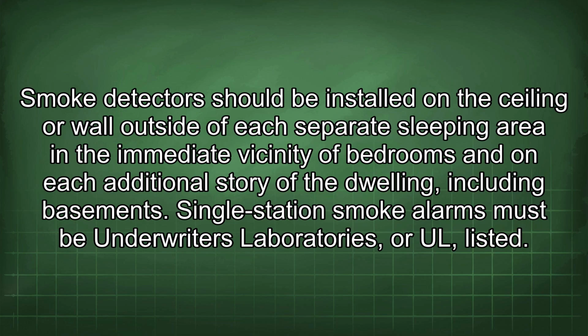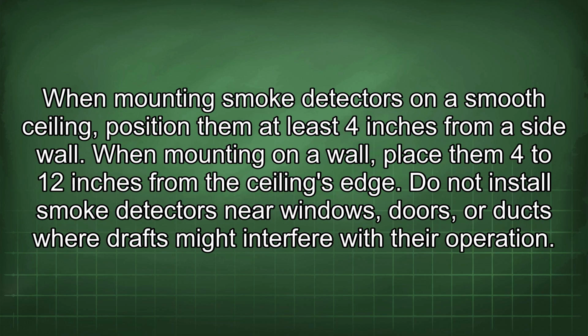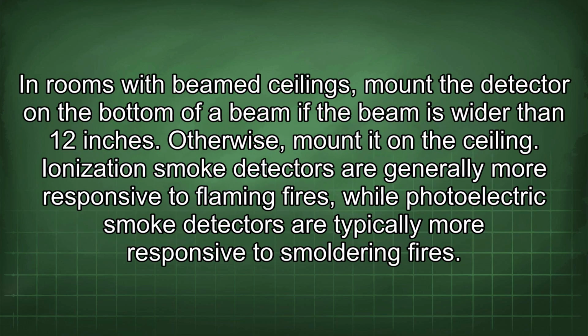Single-station smoke alarms must be Underwriters Laboratories, or UL, listed. When mounting smoke detectors on a smooth ceiling, position them at least 4 inches from a side wall. When mounting on a wall, place them 4 to 12 inches from the ceiling's edge. Do not install smoke detectors near windows, doors, or ducts where drafts might interfere with their operation. In rooms with beamed ceilings, mount the detector on the bottom of a beam if the beam is wider than 12 inches. Otherwise, mount it on the ceiling.